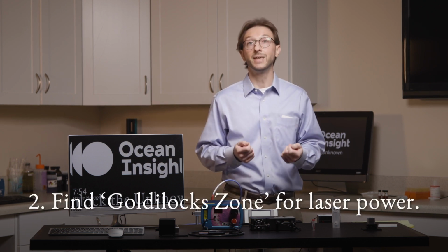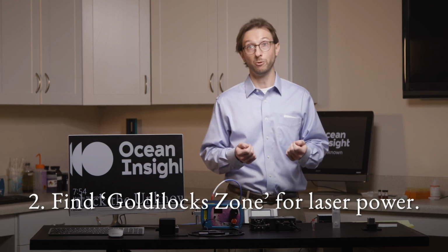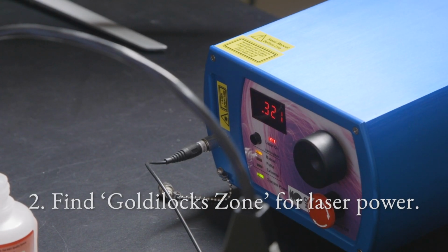Additionally, you need to find that Goldilocks zone for the laser power. If you go too high on the laser power, you're going to burn the sample, and you're going to know that because your spectra are going to go off the charts, and you're going to see smoke physically coming off of your substrate or off of the sample there. On the flip side, if you don't add enough laser power, you're not going to get that photo interaction, you're not going to get that Raman emission that's really going to tell you about your sample.